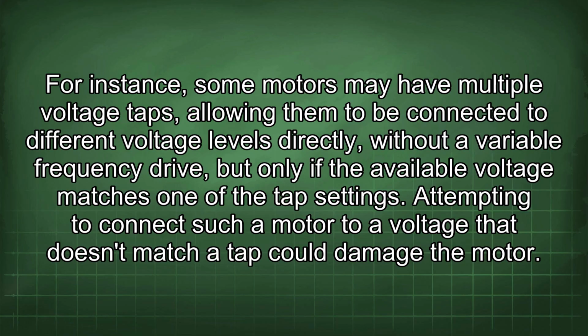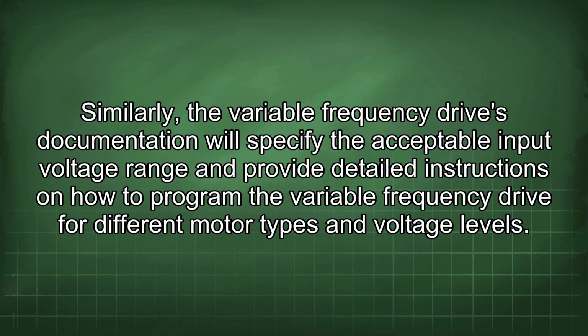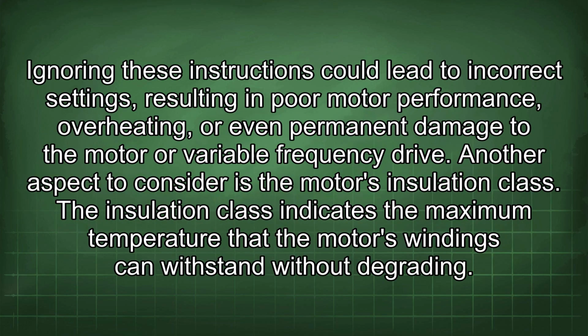For instance, some motors may have multiple voltage taps, allowing them to be connected to different voltage levels directly without a variable frequency drive, but only if the available voltage matches one of the tap settings. Attempting to connect such a motor to a voltage that doesn't match a tap could damage the motor. Similarly, the variable frequency drive's documentation will specify the acceptable input voltage range and provide detailed instructions on how to program the variable frequency drive for different motor types and voltage levels. Ignoring these instructions could lead to incorrect settings, resulting in poor motor performance, overheating, or even permanent damage to the motor or variable frequency drive.